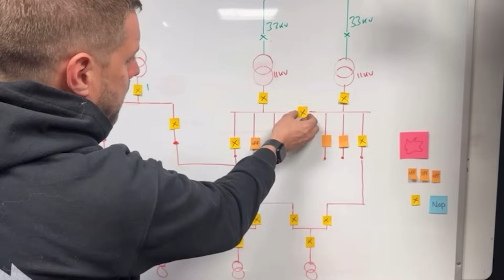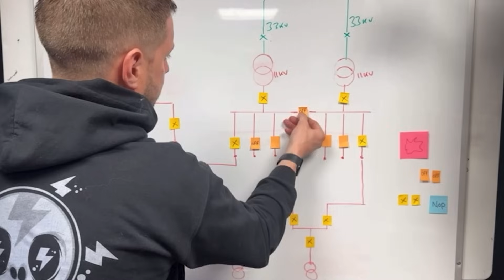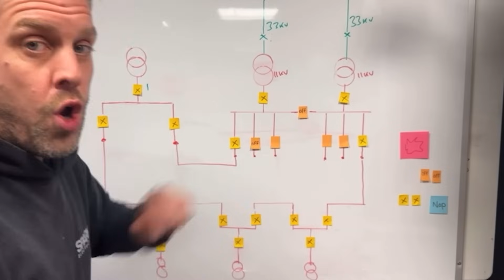Stand by for oddities, because it wouldn't actually be like that. We wouldn't have the bus section closed, we'd have it open, because we wouldn't want double the fault current, two times the transformer, double the fault current, yeah? So the bus section, in normal operation, would be open.